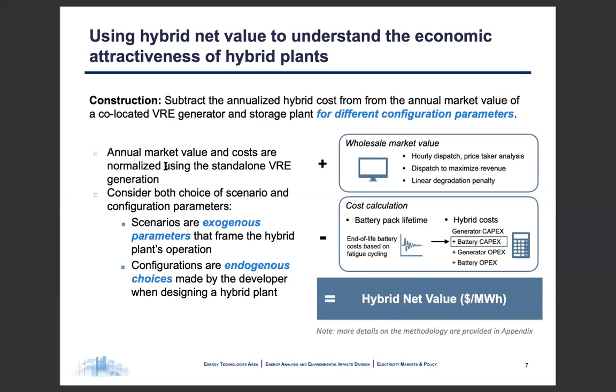For this degradation modeling, we extract from the time series of the state of charge of the battery throughout our optimization the number and depth of cycles using a rainflow counting algorithm, which is typically used to characterize metal fatigue. Then we use design curves for lithium iron phosphate batteries, a common battery chemistry for utility applications, to map the different types of cycles to marginal cycling degradation, or the percentage of nominal capacity loss with each cycling.